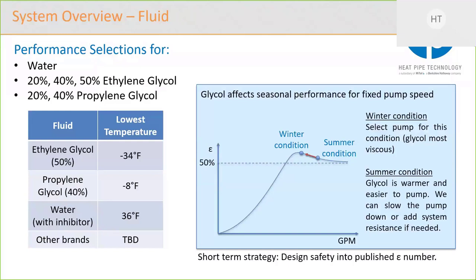Now, I'm also going to walk you through a little chart that shows how the glycol has an effect on that performance. So remember I said in a previous slide that an infinite flow of refrigerant means that you can't get more than 50% effectiveness. That's what I'm showing here. So at the beginning, when you have a very low gallons per minute, your performance is pretty much proportional to gallons per minute. And it gets better and better until it hits a peak. But at that peak, it starts to plateau off and then actually starts to drop. Now, I've squashed this up a little bit to show that the plateau isn't as big as it actually is, just so you can see diagrammatically what's going on here.